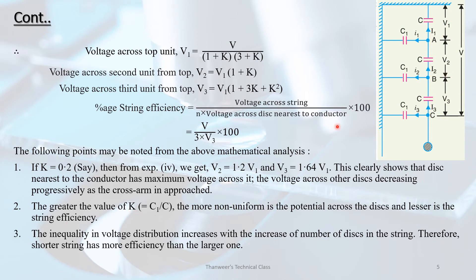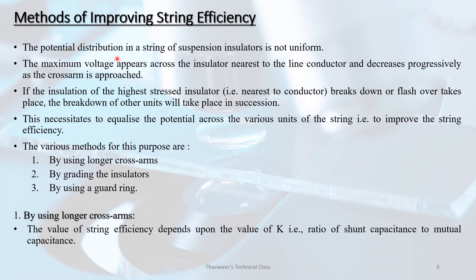The lesser the value of K (ratio of shunt capacitance to self-capacitance), the more uniform is the potential distribution across the disks and the greater is the string efficiency. The inequality in voltage distribution increases with increased number of disks in the string, so a shorter string has more efficiency than a longer one.